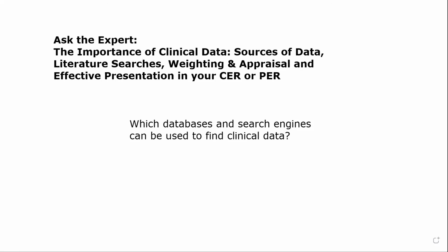They're looking at a minimum, and MedDev actually calls this out, for Embase and Medline. They like to see those two at a minimum, and that's been our experience. We use a platform called ProQuest Dialog. Our librarian and our systematic literature review team use ProQuest Dialog. We use DistillerSR for appraising and reviewing. So I say don't spare your methodology here. It could bite you in the CER and PER. This is a very important part of the CER and PER.